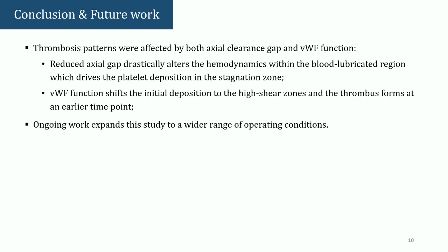This work is very much a work in progress, but so far we have seen that the reduced axial gap can drastically alter the hemodynamic conditions within the blood lubricated region, which drives the platelet deposition in the stagnation zone. Activating the vWF function shifts the initial deposition to the high shear zone, and this happens at a much earlier time point. Ongoing work expands this study to a wider range of operating conditions with corresponding axial positions of the impeller.